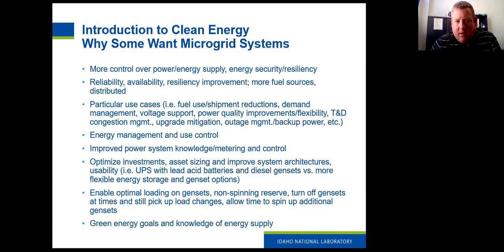And when I have a battery, all my loads can be picked up by one generator, or most of it. Then I can optimally load that, charging or discharging the battery to hit that sweet spot for the generator. The battery can also pick up any extra loads, so I'm not running that second gen set, and I'm able to compensate for that spinning reserve requirement.